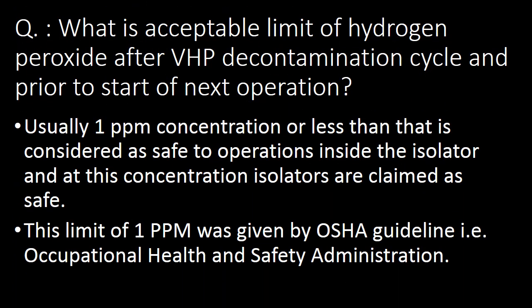Next question: what is the acceptable limit of hydrogen peroxide after the VHP decontamination cycle and prior to the start of the next operation? Usually 1 ppm concentration or less is considered safe for operations inside the isolators, and at these concentrations isolators are claimed as safe. This limit of 1 ppm was given by the OSHA guideline — that is, the Occupational Health and Safety Administration.